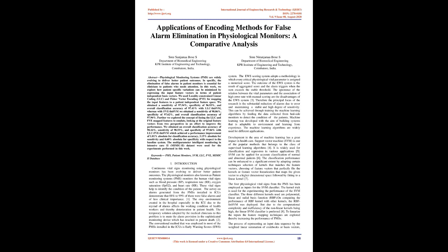The physiological monitors, also known as patient monitoring systems, PMS, monitor the human vital signs such as blood pressure, BP, respiration rate, RR, oxygen saturation, SpO2, and heart rate, HR. These vital signs help to identify the condition of the patient. The survey on alarms generated from PMSs installed in ICUs demonstrates that 88% to 99% of them were false alarms and of less clinical importance.